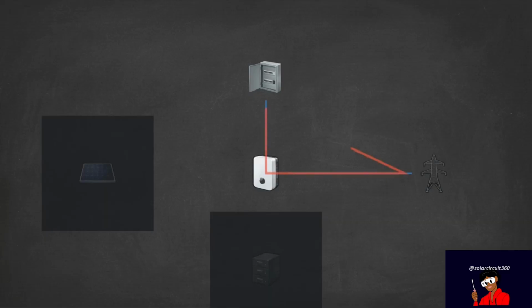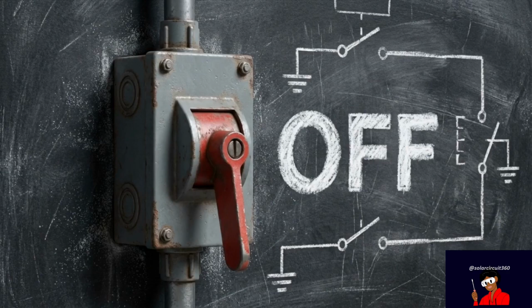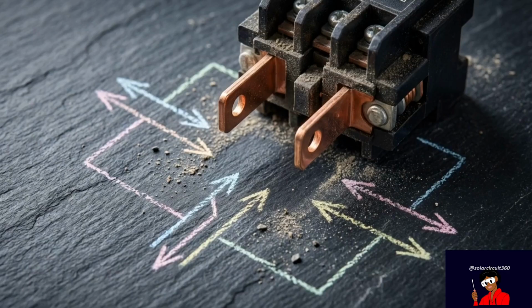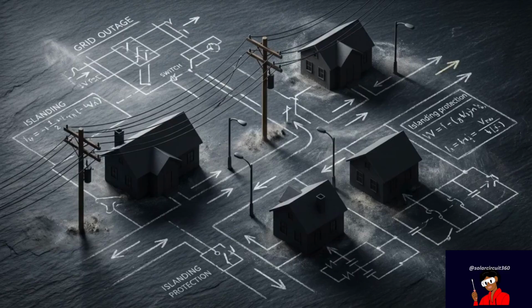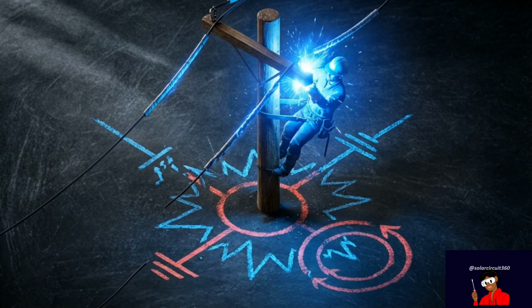The grid connection introduces a topology risk. If grid-tied and off-grid alternating current are improperly bonded, it creates a dangerous grounding fault loop. The system must also utilize anti-islanding protection. This is an automatic safety protocol that stops the inverter from pushing reverse current onto a downed electrical grid during a blackout. Improper grid synchronization introduces lethal shock hazards to both the homeowner and utility line workers.